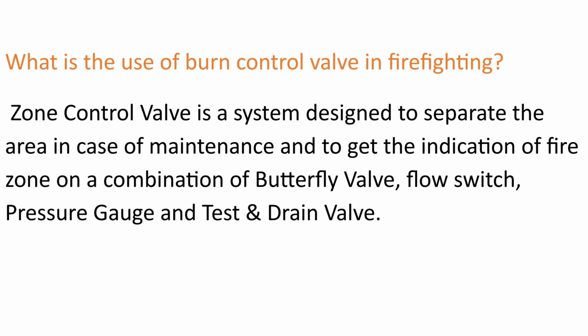What is the use of a zone control valve in firefighting? A zone control valve is a system designed to separate the area in case of maintenance and to get the indication of the fire zone, made up of a combination of butterfly valve, flow switch, pressure gauge and test drain valve.